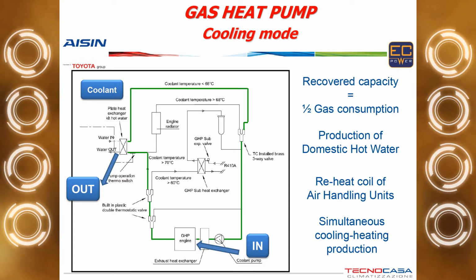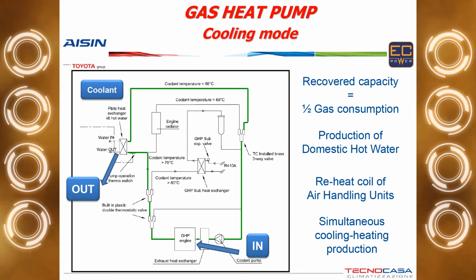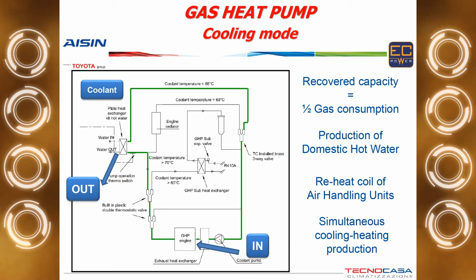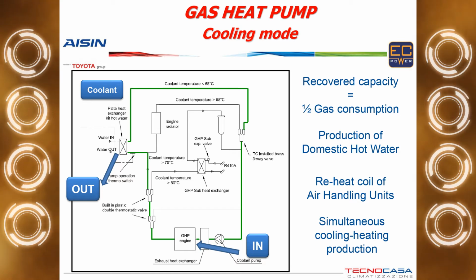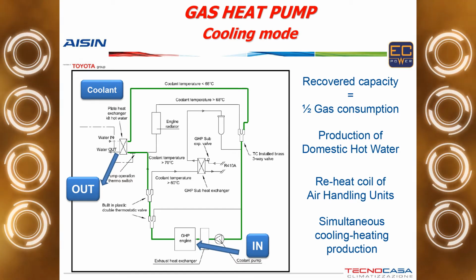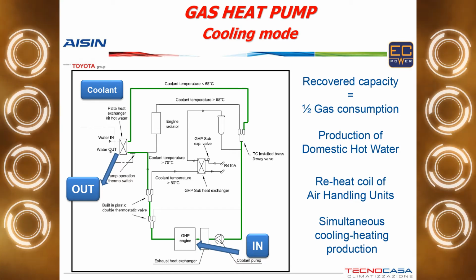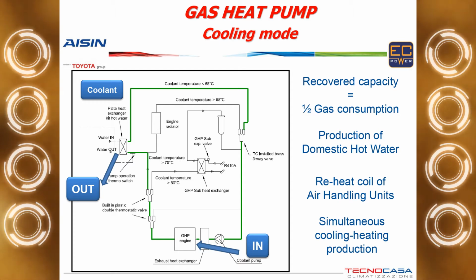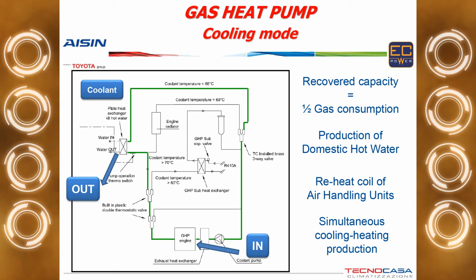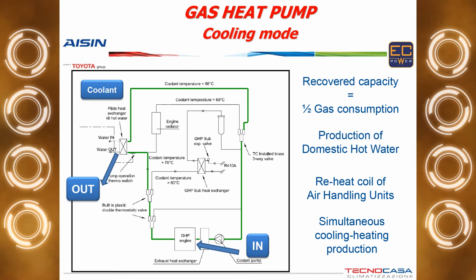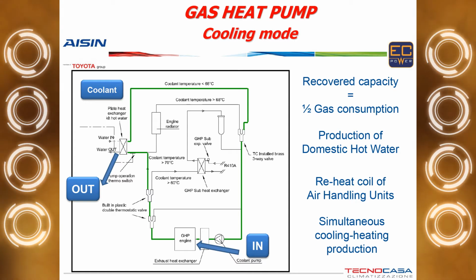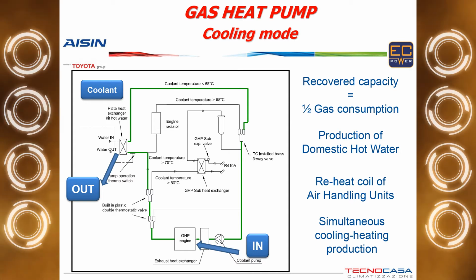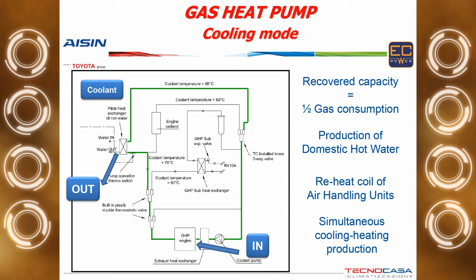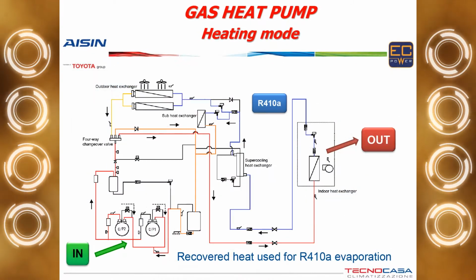The presence of the domestic hot water kit does not affect the capacity nor the consumption of the heat pump. So this quota of energy that we get is completely for free. We can recover in cooling mode half of the gas consumption. It's a variable speed heat pump, so it depends on how much we are using at the moment. We can always recover half of what we are using.